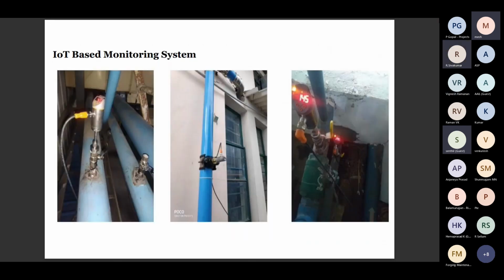So this is a compressor pipeline. In the existing pipeline, this mass flow type of sensor was fitted, and one pressure sensor is fitted in another line. A half-inch ball valve is used. The sensor length is only 200 mm, so the sensor has to be inserted a minimum of 15 to 20 mm inside the pipeline, so that the air generated, at what CFM your compressor gives, can be exactly monitored by the system.